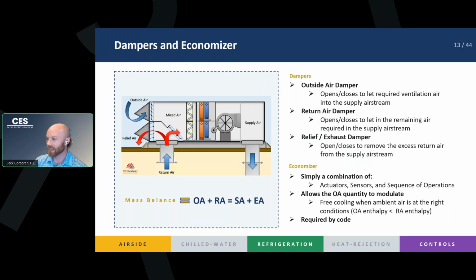But how does that get set? We all know that we need to have a certain amount of outside air per code, right? So our outside air damper on the left side of this image opens and closes to let in the required outside air, right? It's going to let in 20% of your air as outside air, and the other 80% is going to be let in as return air. There has to be some sort of sequence of dampers that open and close or are set at a fixed level that'll allow that outside air to come in at 20% and your return air to come back to the unit at 80%. But where does the other 20% of the return air go? It has to be spilled out, right? And that's all part of the mass balance equation. That is spilled out of the building as relief or exhaust air, and the exhaust or relief damper is what allows that to be balanced to the correct CFM.